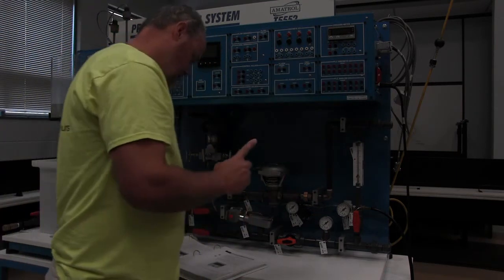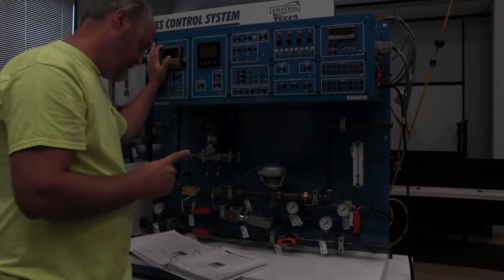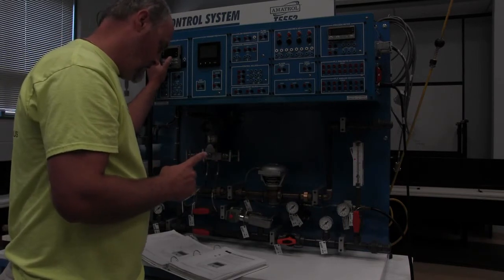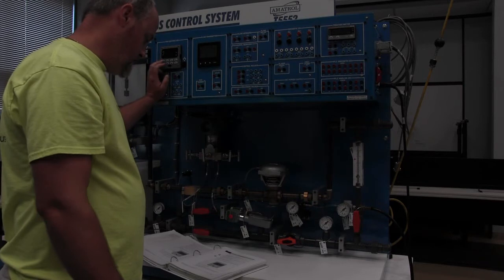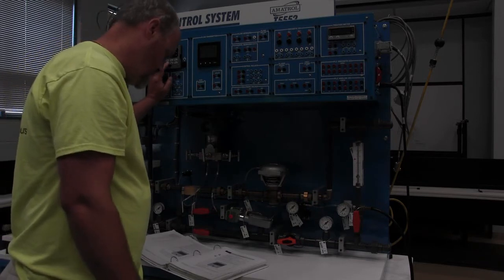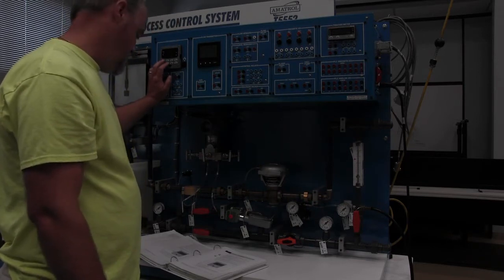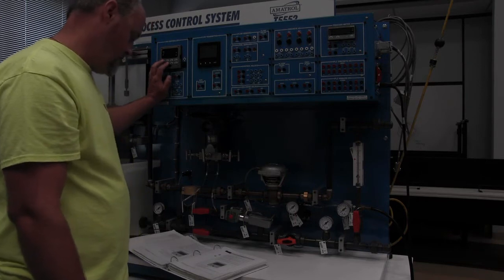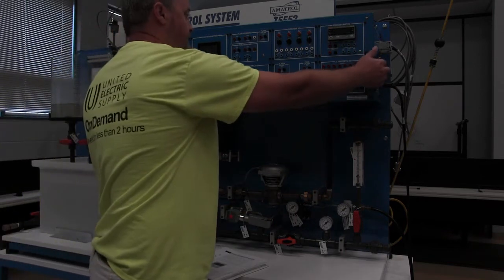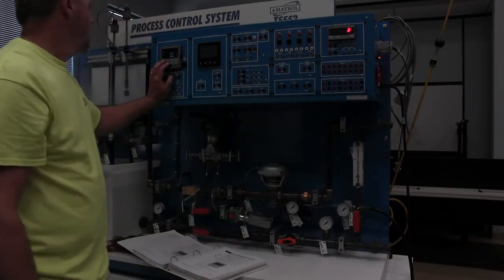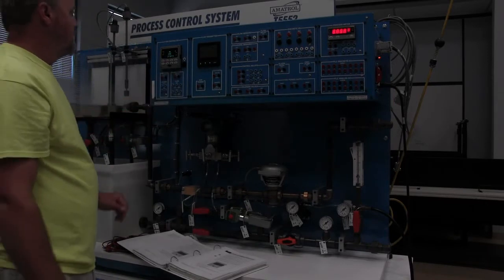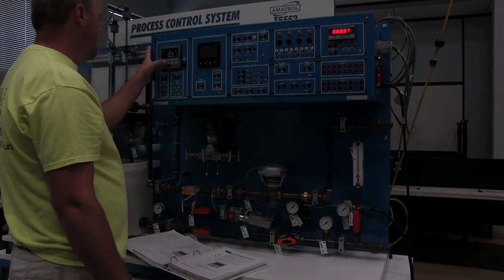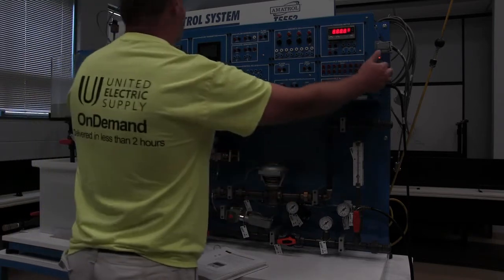So we're going to turn the main circuit breaker on. While the test done light is on, we're going to press the function loop and the up arrow at the same time. And that's going to bring us to our factory restore screen. So we're going to see update. That didn't work.